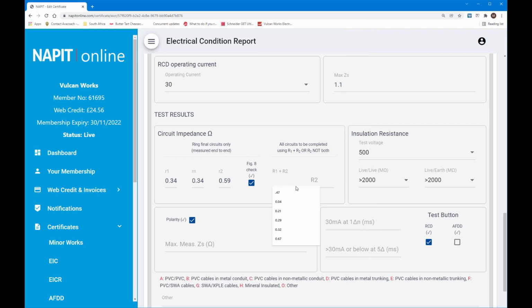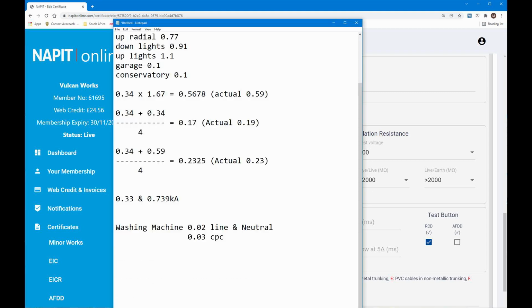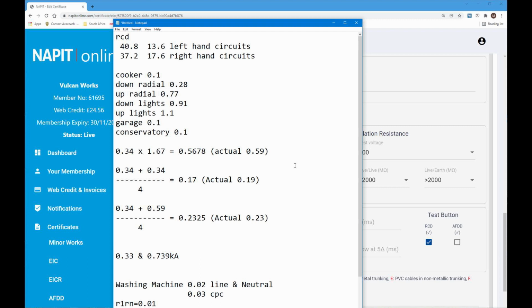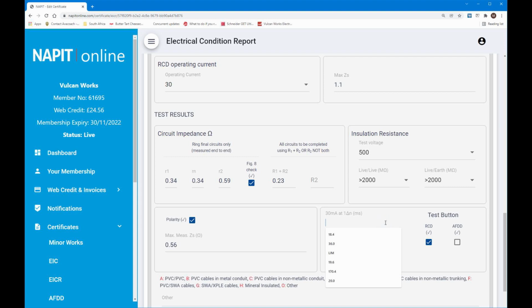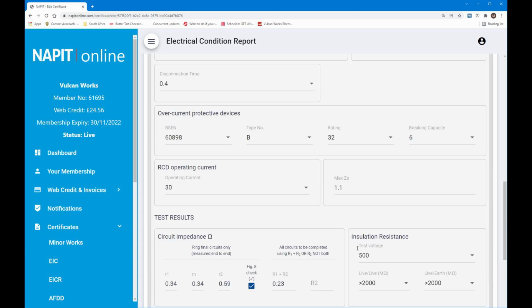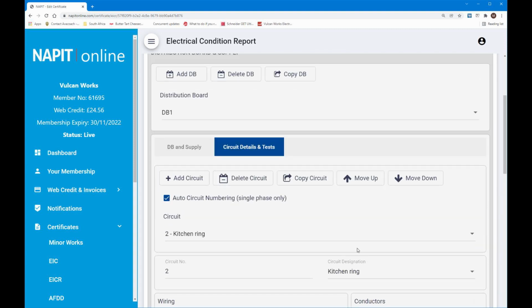So in here we put down 0.23, and then we add that to the 0.33 ZE, and we get 0.56, which is well within the maximum ZS. And then finally we're going to fit in the RCD readings for this, which is 40.8 and 13.6. That completes everything on that particular board.